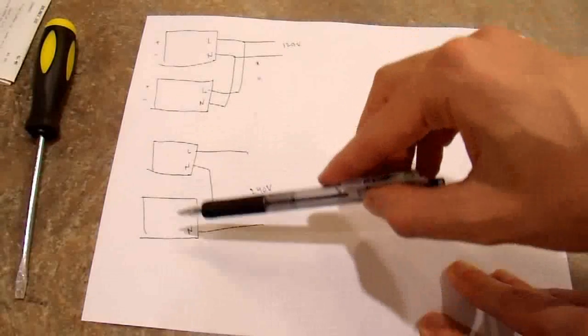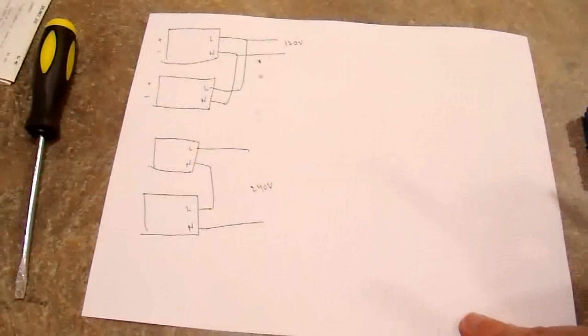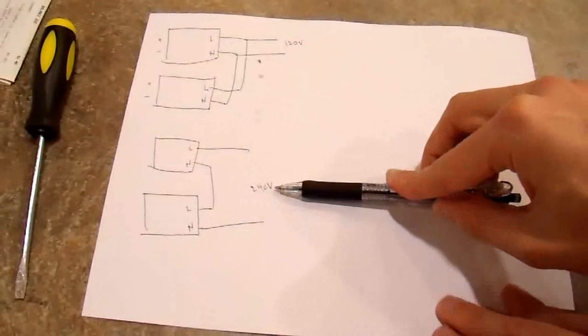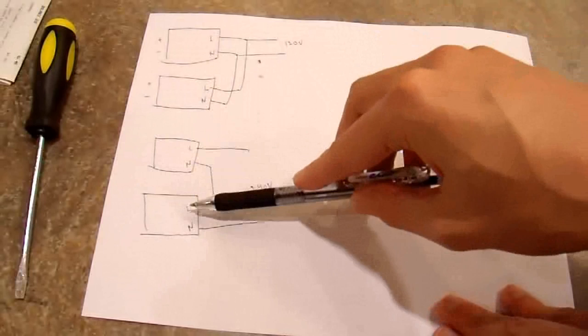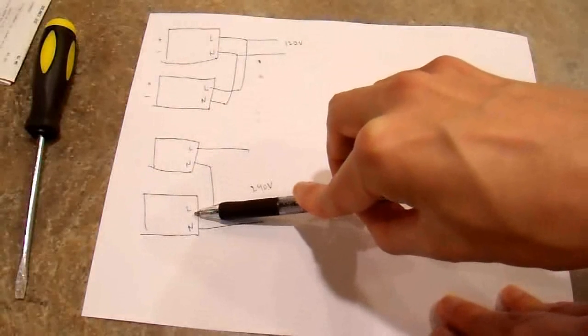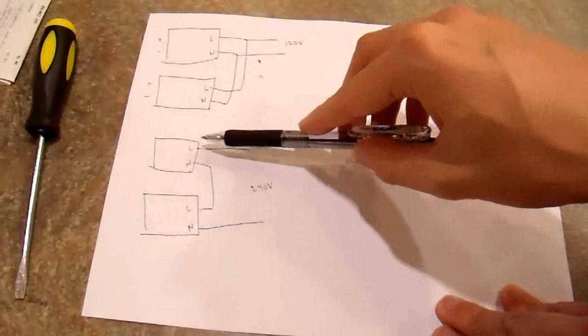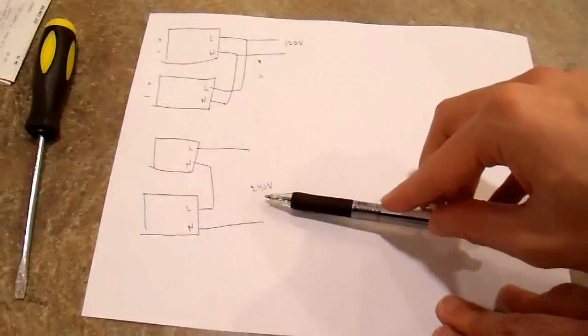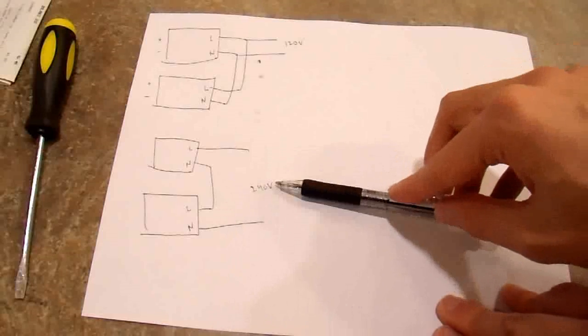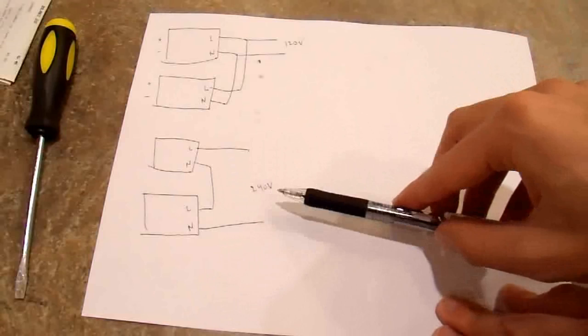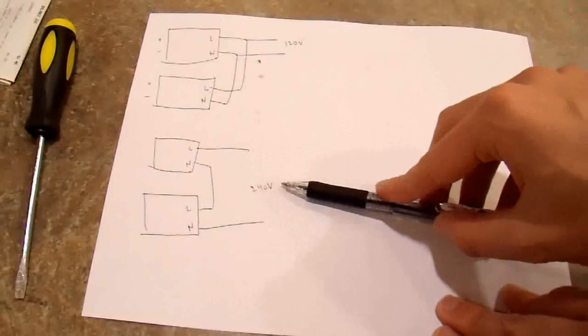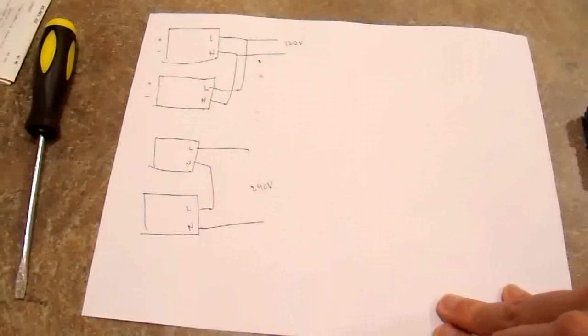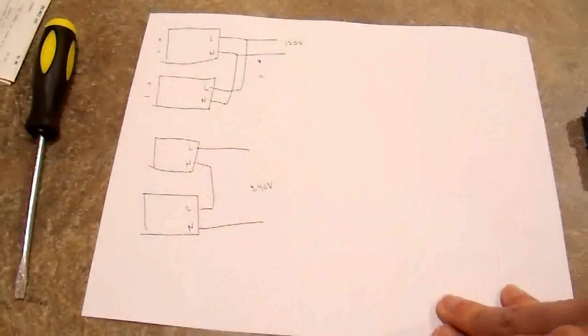However, they still need to be synchronized. If they're not synchronized, then you won't end up with a stable 240-volt output. For example, if this one is at 60 hertz and this one is at 59.9 hertz, something slightly different than this one, if they're not perfectly synchronized, you'll end up with an output voltage that very slowly oscillates between 0 volts and 240 volts. It'll still be about 60 hertz, but it'll slowly oscillate between 0 to 240, go back down to 0, back up to 240, and it won't be a usable output voltage. So they do need to be synchronized.